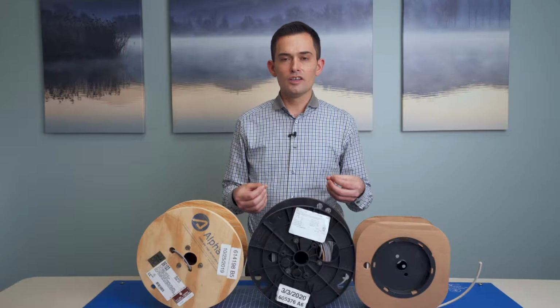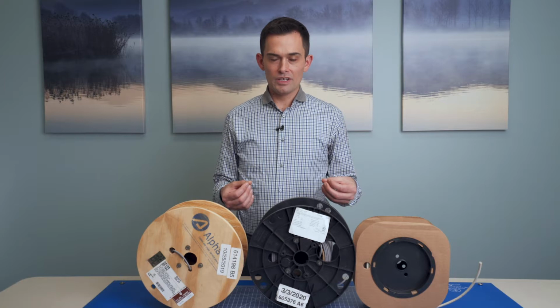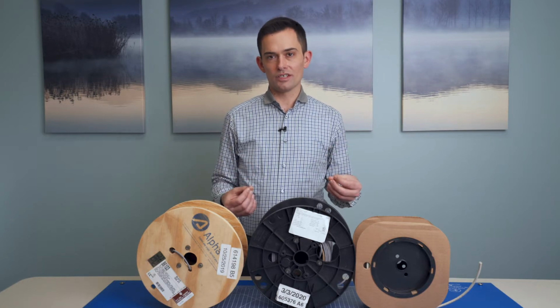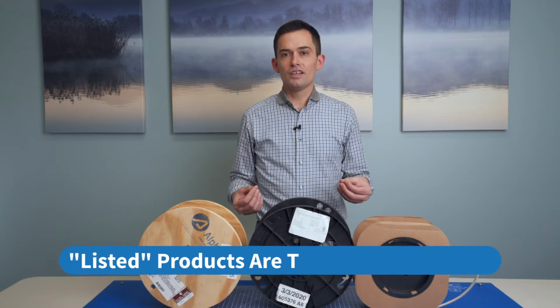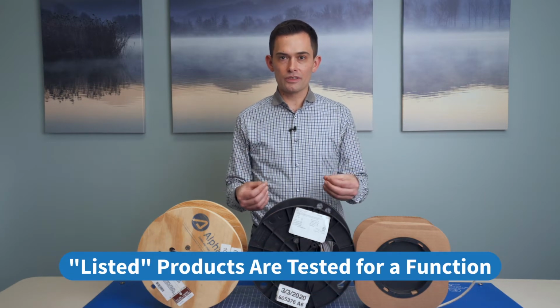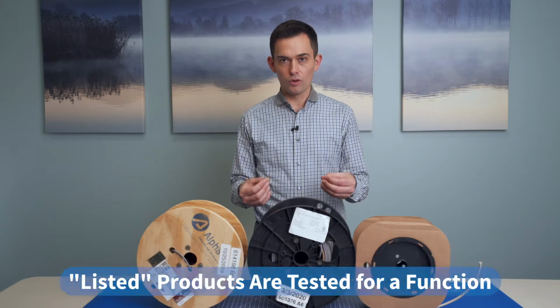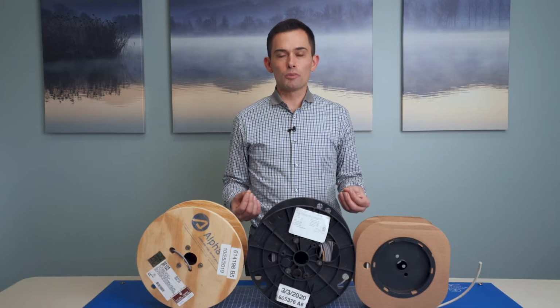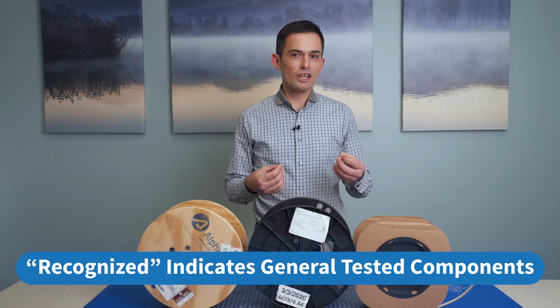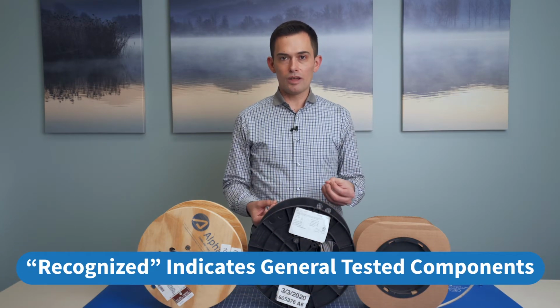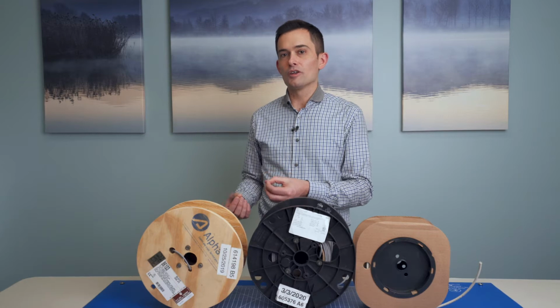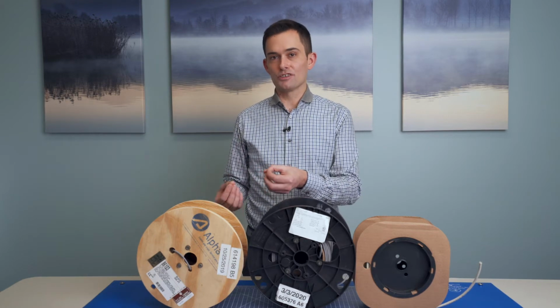consumer goods. The main difference between these two is how UL performs the testing. UL can only list a product if they're able to test the specific function that the item was designed to perform. Things like components carry a UL recognized marking because they have a general purpose and UL is not able to know every single application or environment in which that item could be installed in.